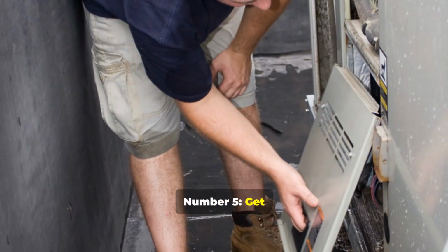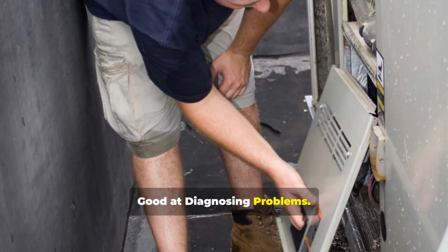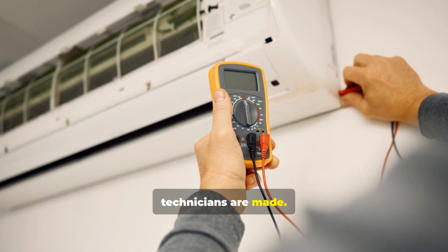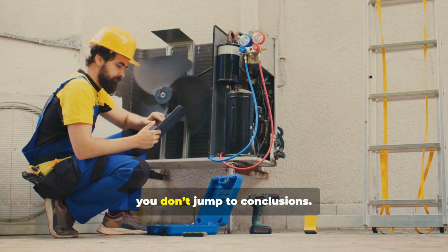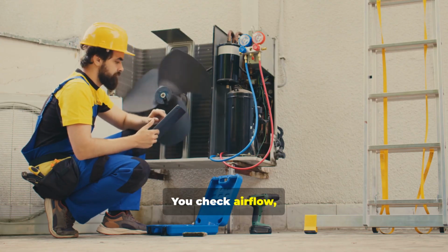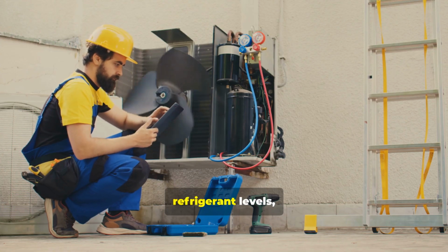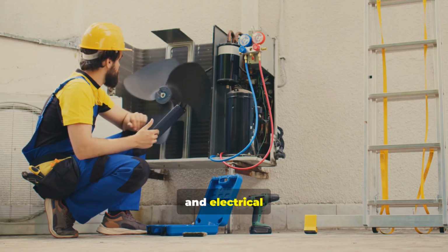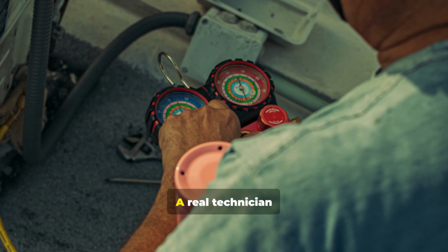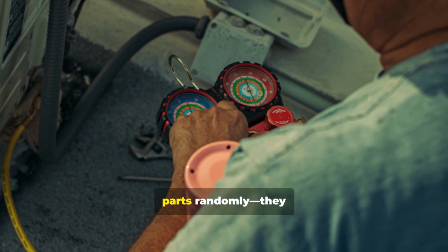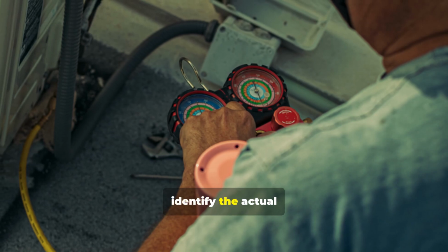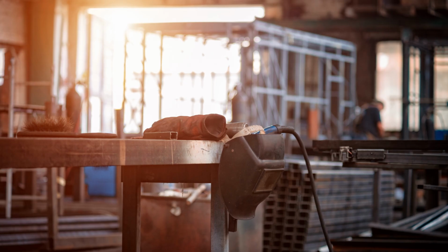Number 5: Get good at diagnosing problems. Diagnosis is where technicians are made. When a system isn't cooling, you don't jump to conclusions. You check airflow, static pressure, refrigerant levels, temperature splits, and electrical components step by step. A real technician doesn't replace parts randomly. They identify the actual failure with proof.